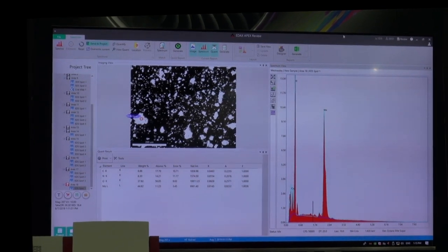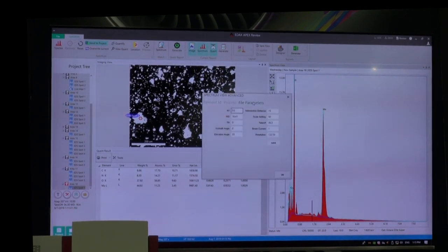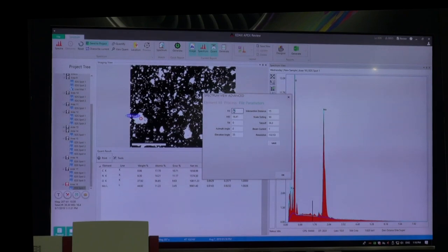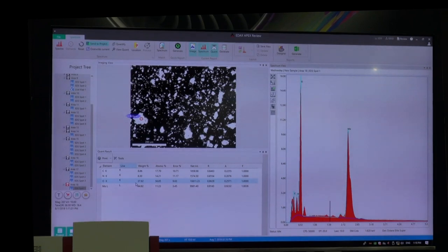You're cutting out some of the additional information you would get in the Bremsstrahlung model — that a bad fit means don't click the quant button, or that background cutting off indicates charging. Right now we pull the acceleration voltage from the microscope; at 10 kilovolts the model assumes landing voltage is 10 kilovolts. You can see from the background tail whether it's actually 10 kilovolts. If you know the true landing voltage is 8 kilovolts, you can go in and update the file parameters so everything recalculates with 8 kilovolts.